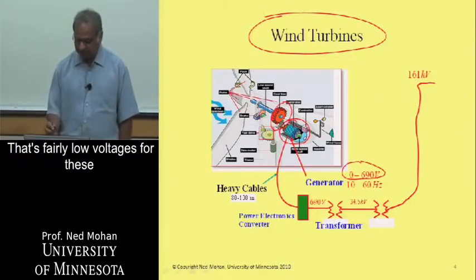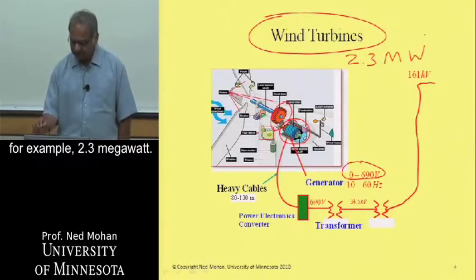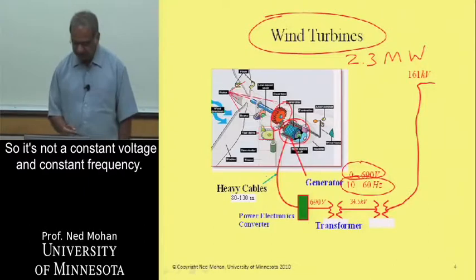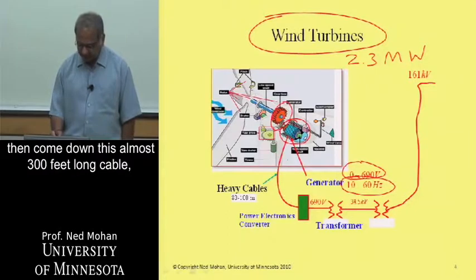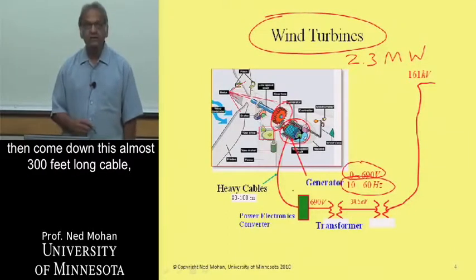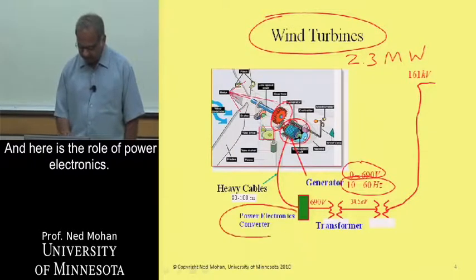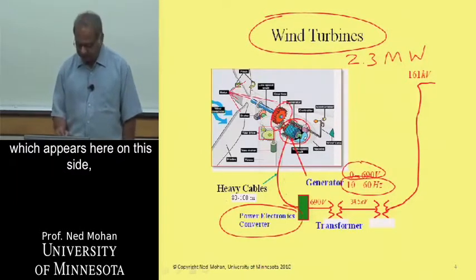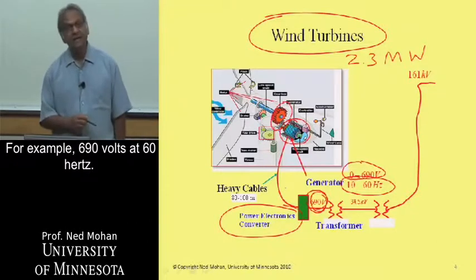It's fairly low voltage for these very high-power wind turbines — for example, 2.3 megawatts — and the frequency could also vary. So it's not a constant voltage and constant frequency, and very large amounts of current then come down this almost 300-foot, 100-meter-long cable. Here is the role of power electronics: we need to convert this variable frequency, variable voltage to a fixed frequency and fixed voltage — for example, 690 volts at 60 hertz.